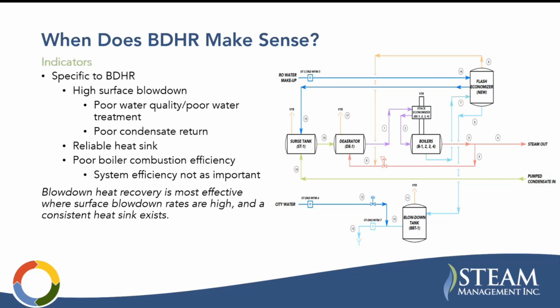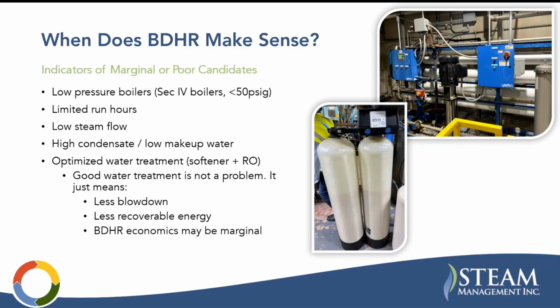Blowdown heat recovery generally is going to be most effective where surface blowdown rates are high and a consistent heat sink exists. Some indicators of marginal or poor candidates: if you have lower pressure boilers, any Section 4 boilers, these are pretty rare to see. But generally, even under 50 pounds, they're going to start falling off. Limited run hours, low steam flow. I would say maybe 20,000 pounds per hour or up is where I'm really leaning towards looking at this.